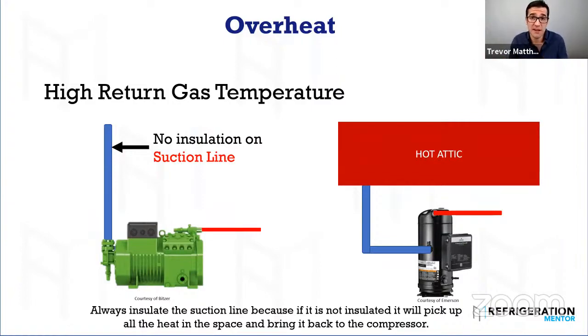And these compressor manufacturers make good compressors. It doesn't matter which one it is. They all make really good compressors. The large manufacturers like Bitzer, like Copeland, like Danfoss, like Tecumseh, they make good compressors. The problem is that we break them or the customer breaks them, by not doing the maintenance, by not servicing the product, by not installing the product correctly. Compressors should be lasting 10, 15, 20 years, not 2 weeks, not 6 months.